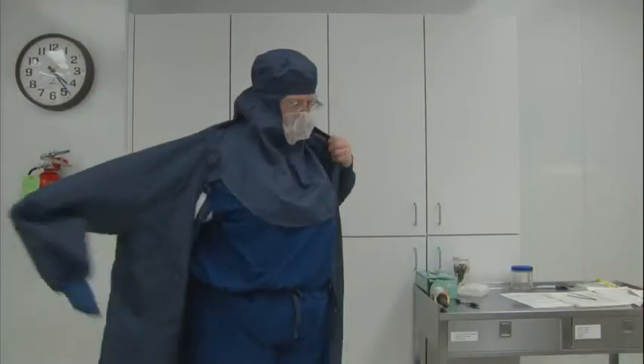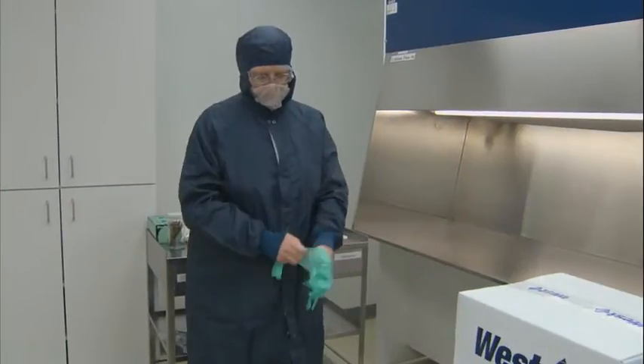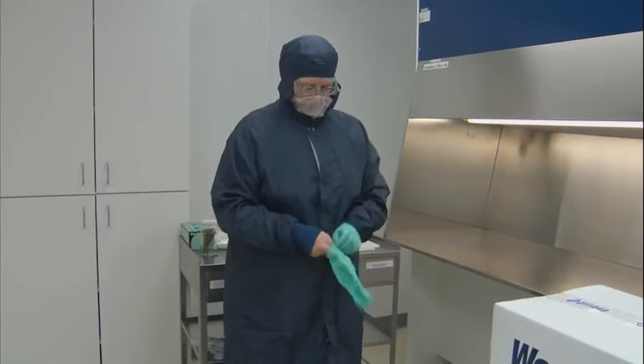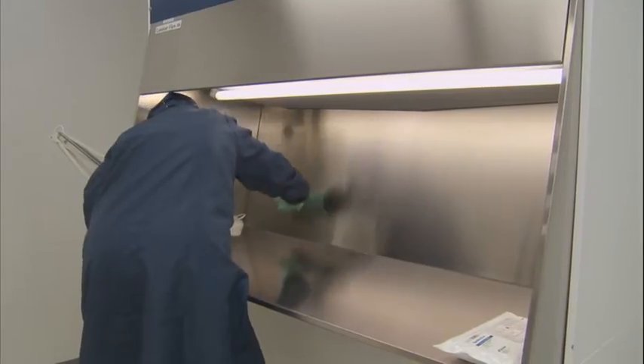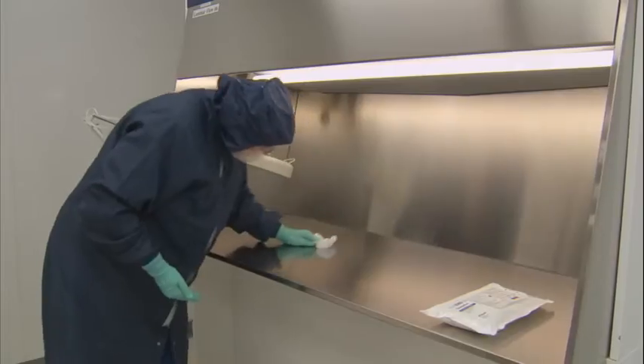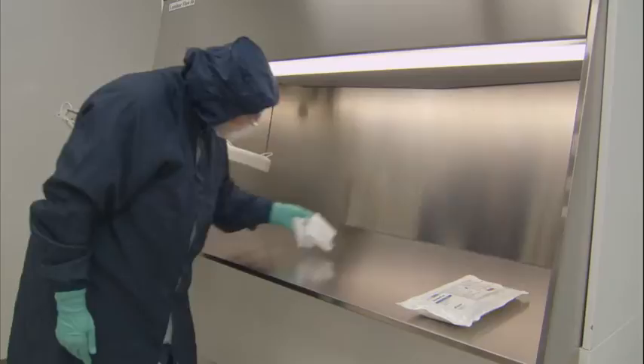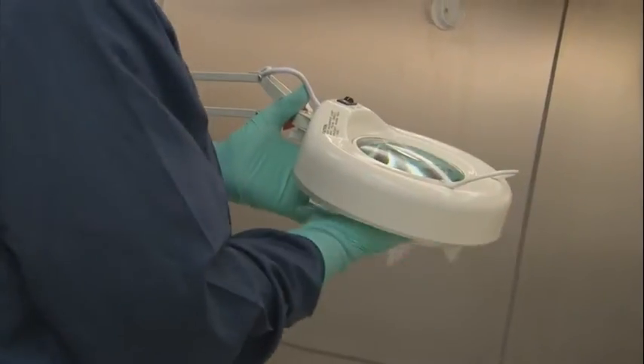The inspector should be properly gowned and the inspection area must be clean from debris that can potentially contaminate the components. The inspector uses commercially available lint-free alcohol wipes to clean the laminar hood in preparation of the inspection process. Ensure the area is clear of all previously inspected items and batches. The area is cleaned prior to beginning inspection to assure there is no cross-contamination of foreign matter.